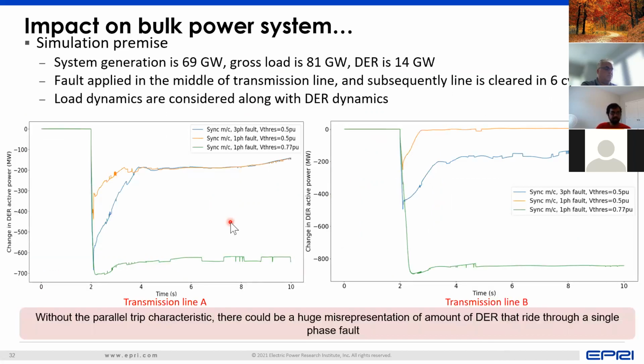And where that is important to consider is if you now see this at a transmission level, where we had a system where we had around 14 gigawatt of DER applied throughout the entire network, and we applied a single phase event in the middle of the transmission network. If you have a three-phase fault, then the DER trips in a certain manner as shown by the blue line, and it's what we would see for a detailed distribution network also. But if you don't change the trip characteristics and you apply the same trip characteristics but apply a single phase fault, in some cases the model may show the same amount of DER tripping.